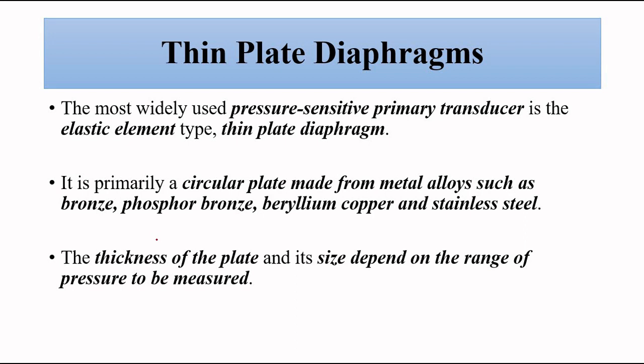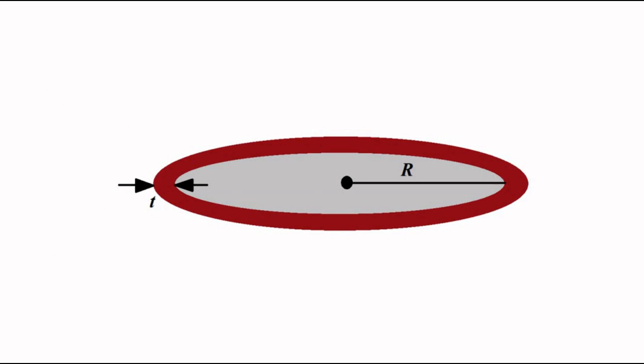Commonly used secondary transducers are LVDT, capacitive transducers, potentiometer, magnetostrictive transducers, or inductive transducers, so that we get a proper voltage or current signal. Again, there has to be a proper calibration between the secondary transducer output and the primary transducer output. So that is the basic principle. Coming back to thin plate diaphragms, it is a primary mechanical transducer. It is, as the name suggests, a thin circular plate made of special metallic alloys.